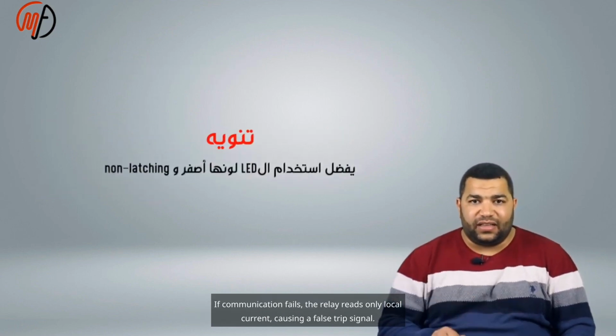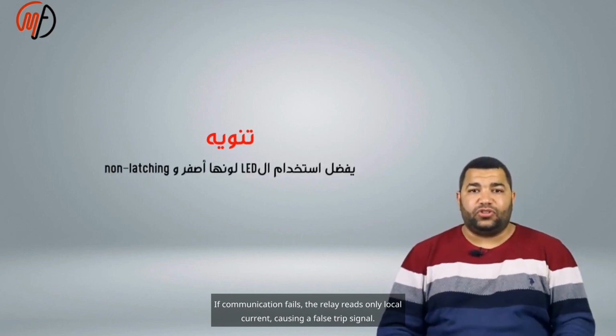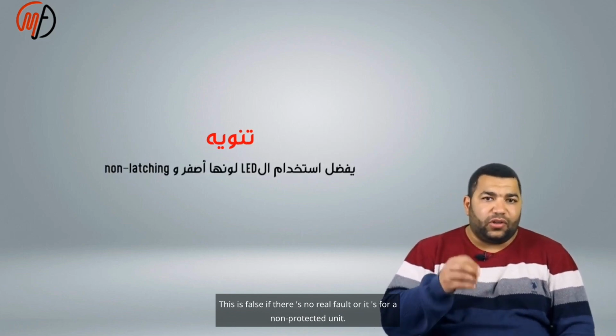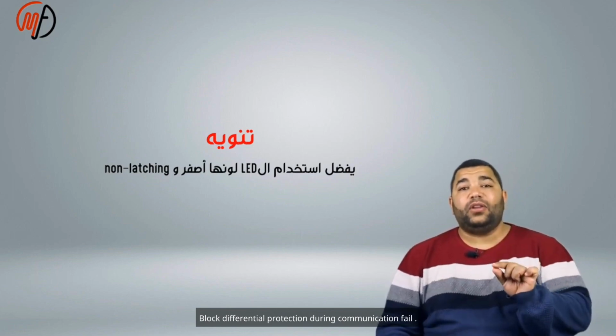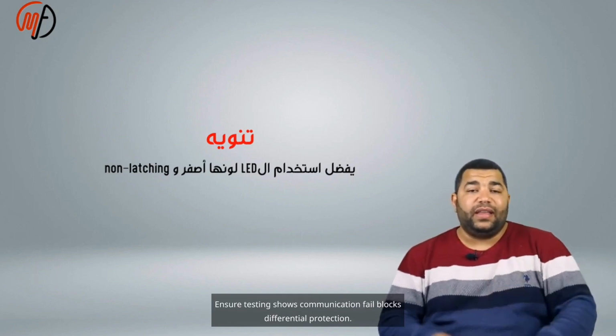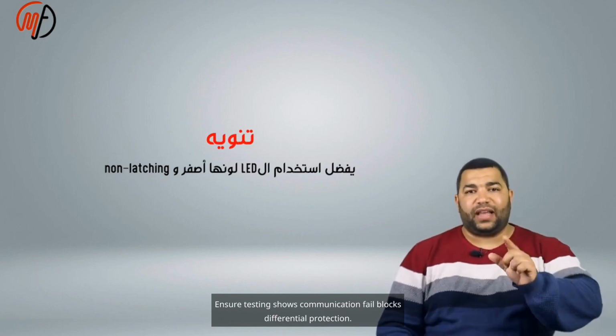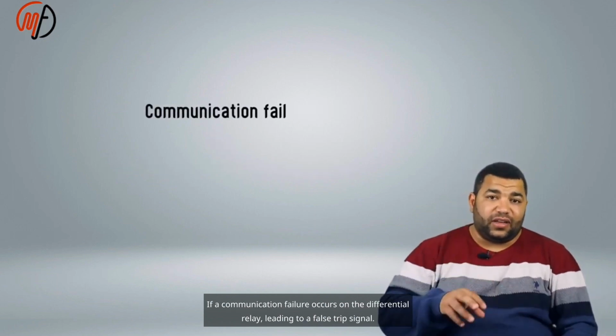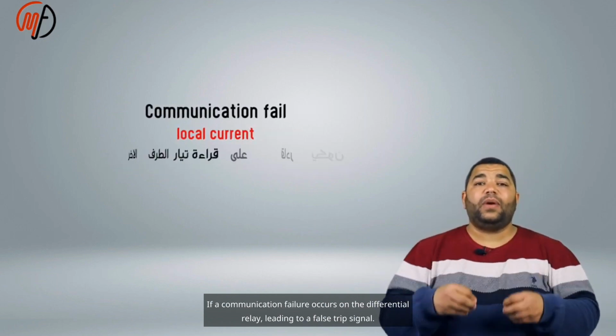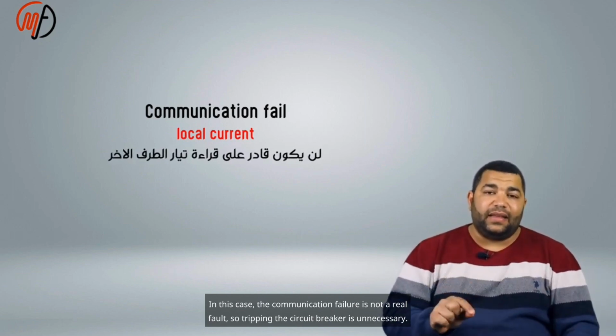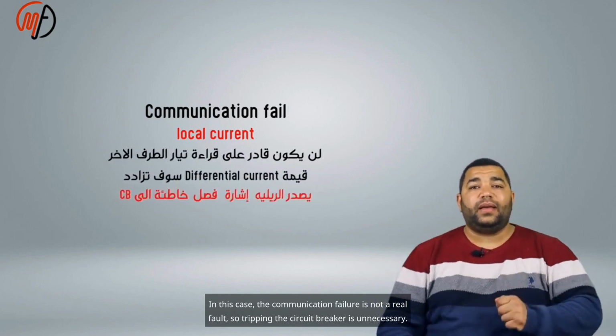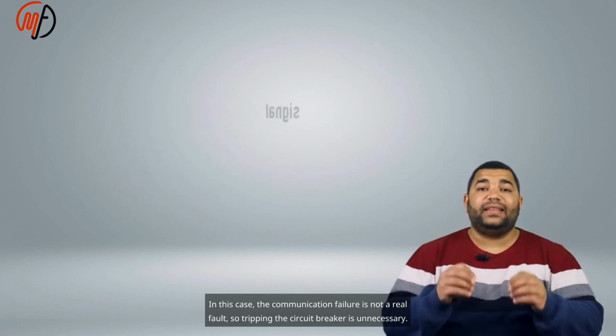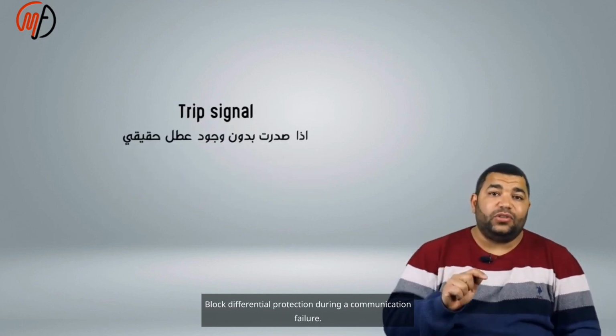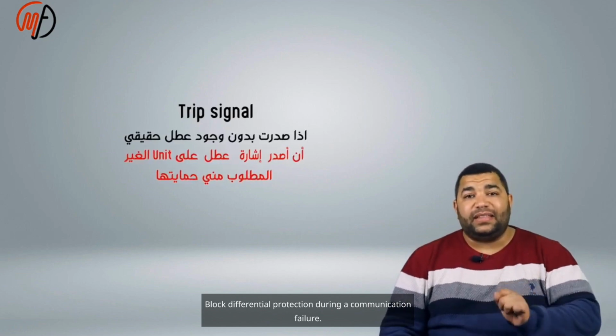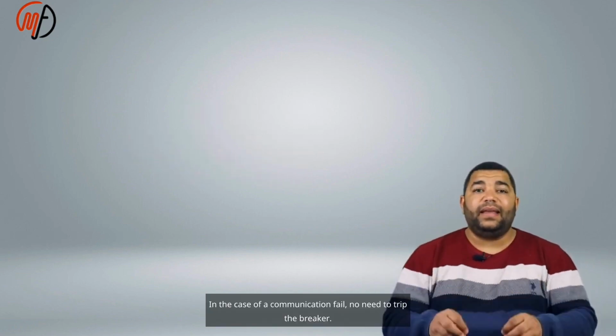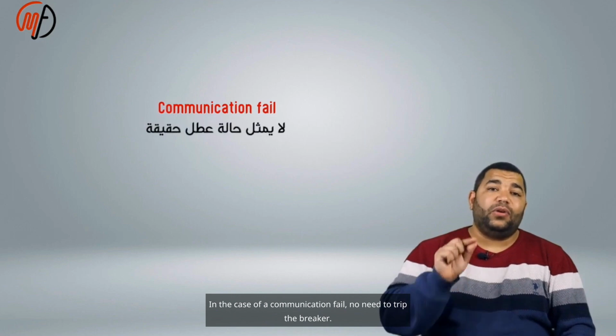If communication fails, the relay reads only local current, causing a false trip signal. This is false if there's no real fault, or it's for a non-protected unit. Block differential protection during communication fail. Ensure testing shows communication fail blocks differential protection. If a communication failure occurs on the differential relay, it leads to a false trip signal. In this case, the communication failure is not a real fault, so tripping the circuit breaker is unnecessary. Block differential protection during a communication failure. Emphasize failure, not alarm. In the case of a communication fail, no need to trip the breaker.